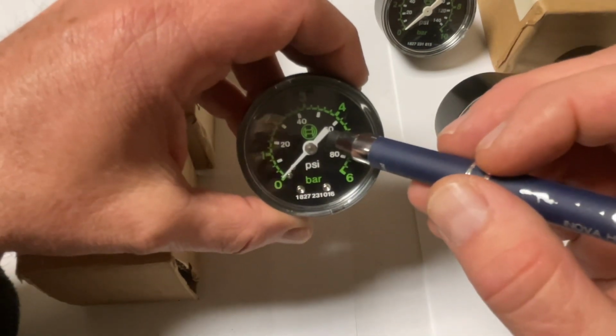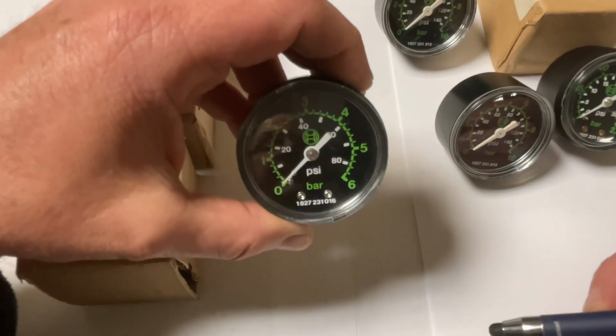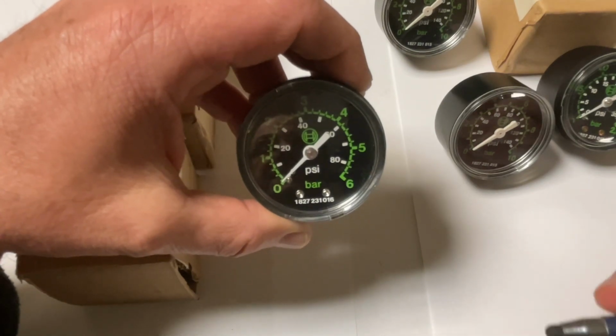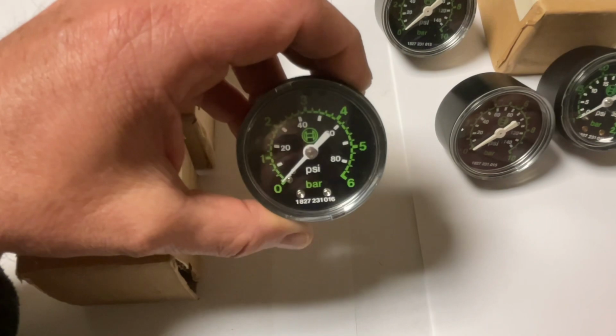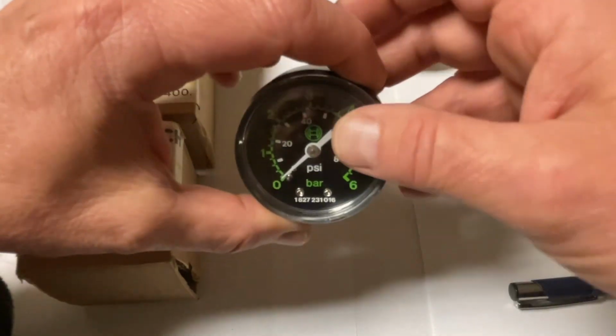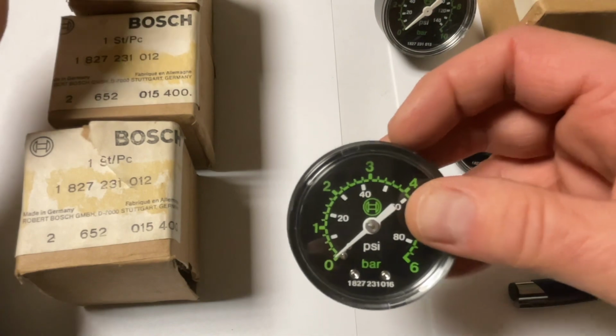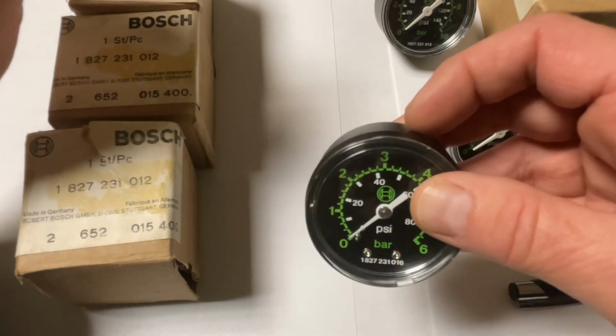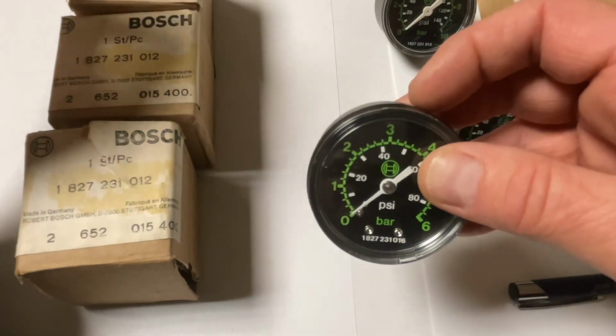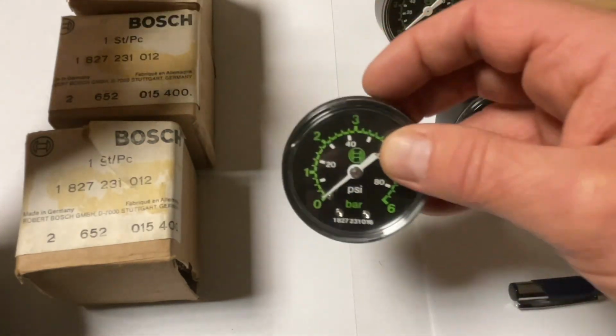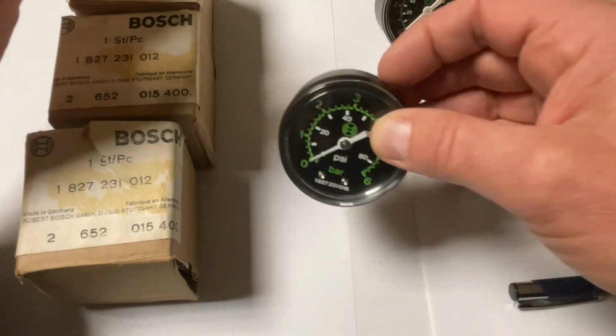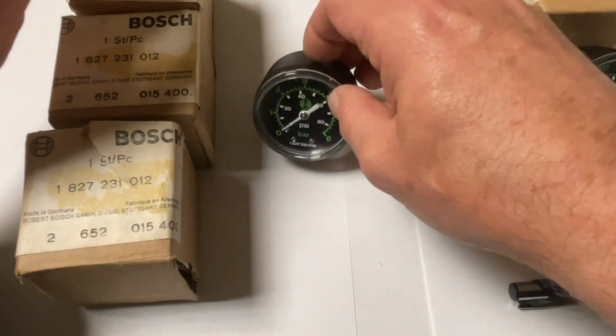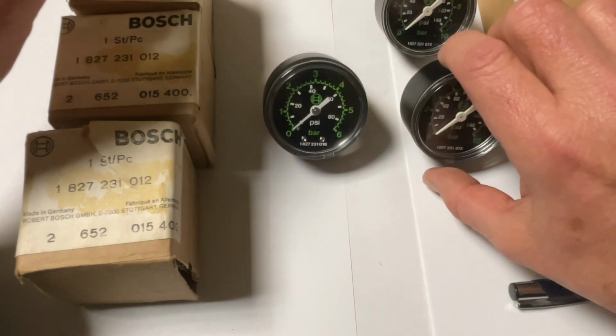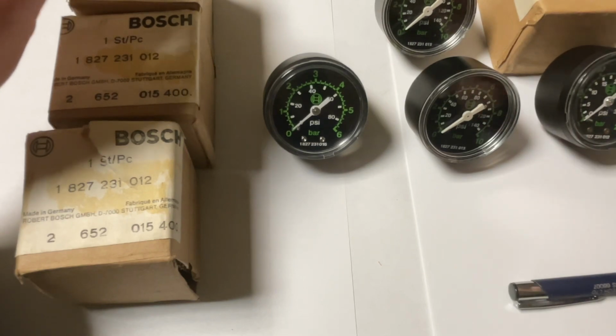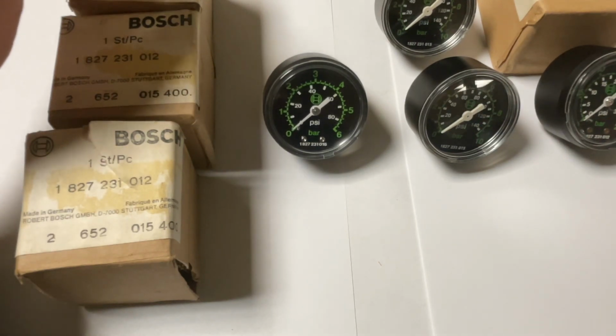So even when they age over time, you can calibrate them exactly to the position, and then the tolerances of those are going to be 1% or less. So they're highly accurate, and they can be calibrated at any time for verification, to make sure that you're working with absolutely correct instruments here. They're high precision, Bosch made in Germany, only for Bosch internal use. On certain items or test systems which were delivered to subcontractors who made parts for Bosch, which didn't happen very much in the 70s and 80s.